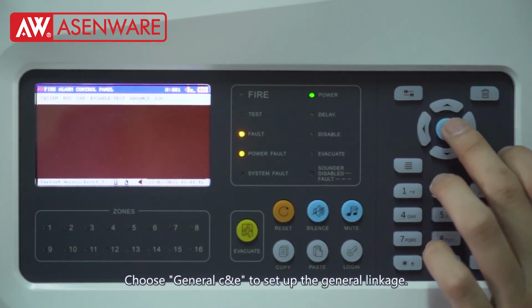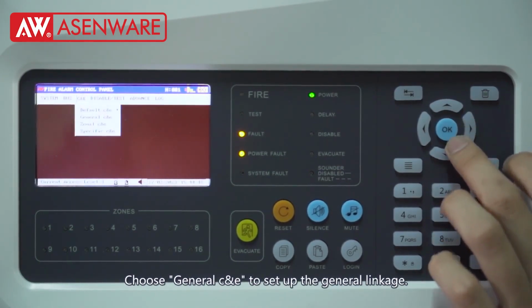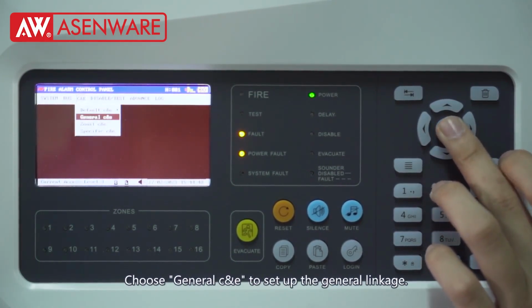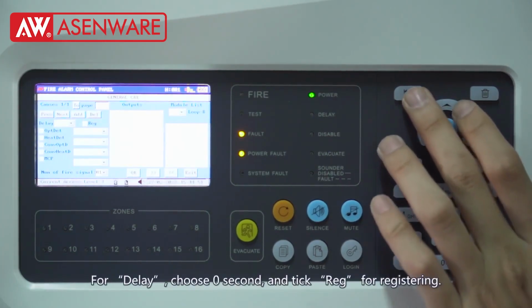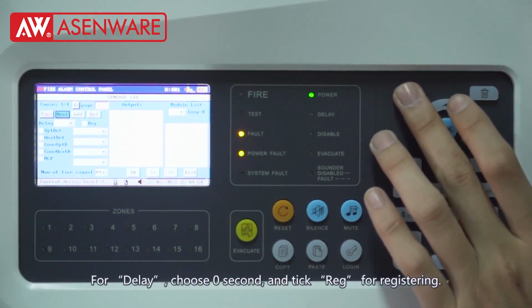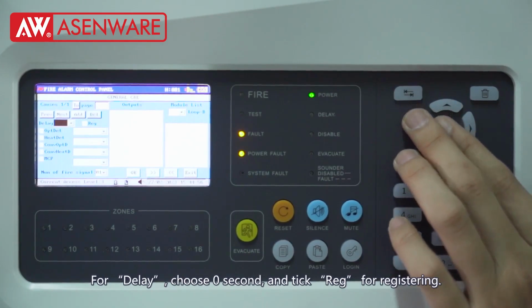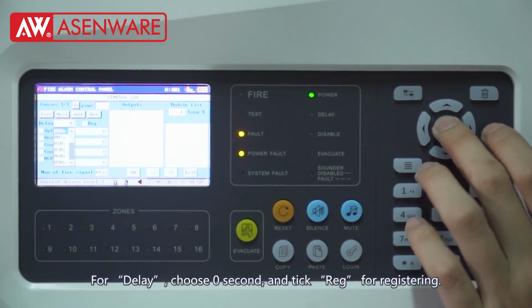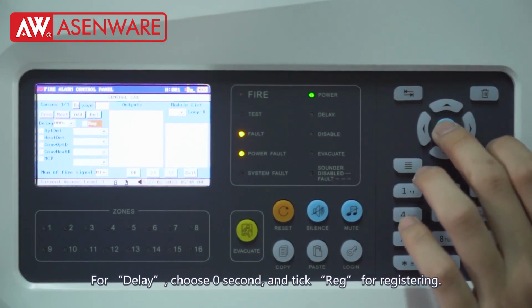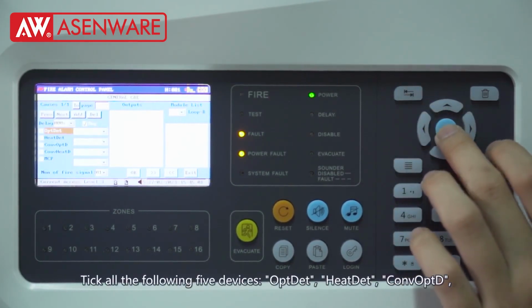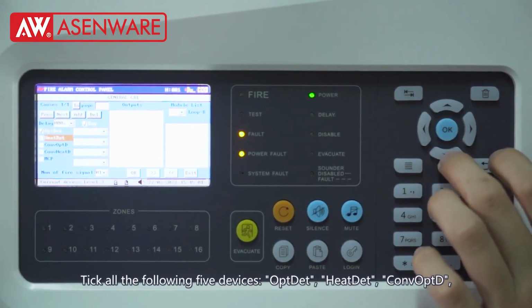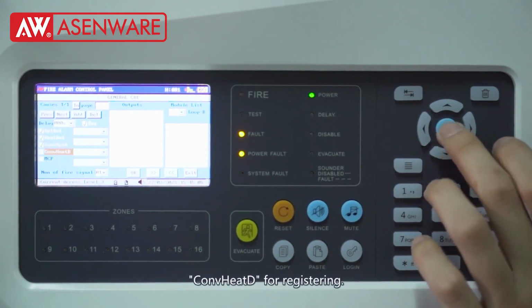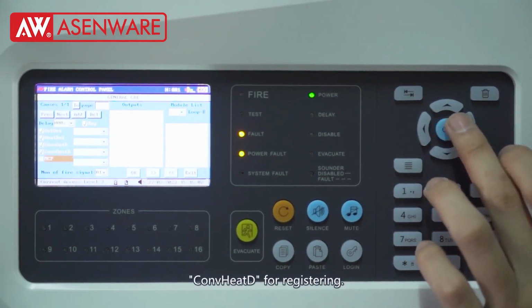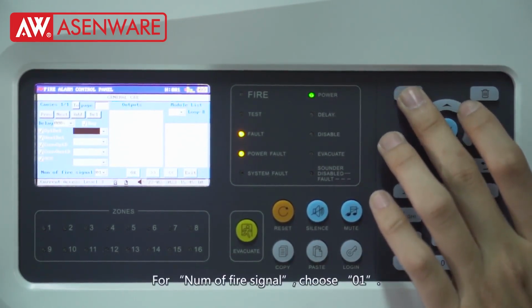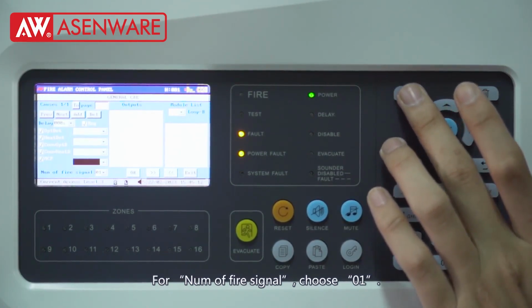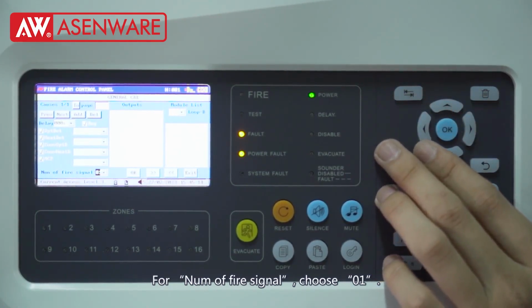Choose General C&E to set up the general linkage. For delay, choose 0 second and tick "Reg" for registering. Tick all the following five devices: op detector, heat detector, conventional op detector, conventional heat detector for registering. For number of fire signal, choose 01.